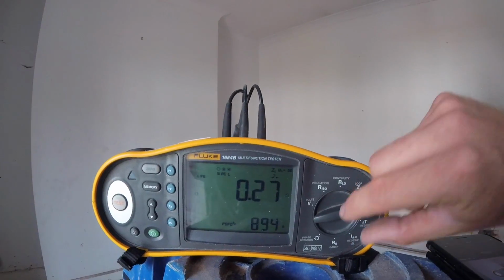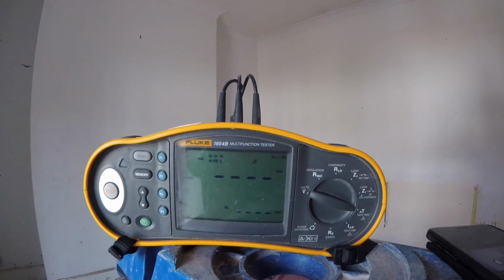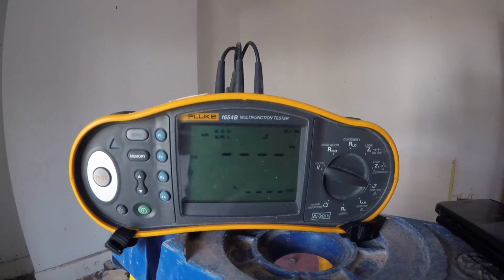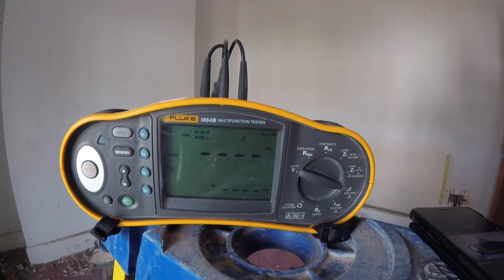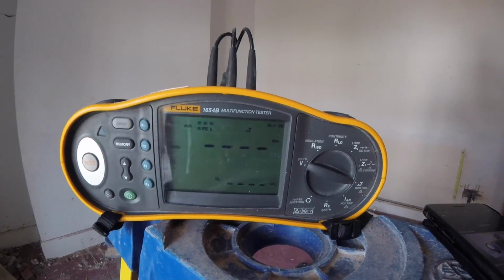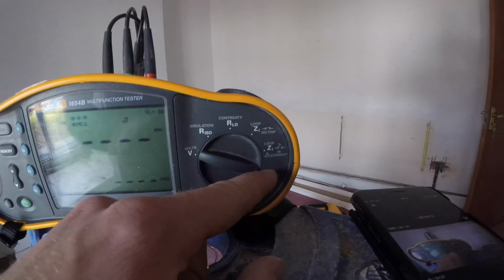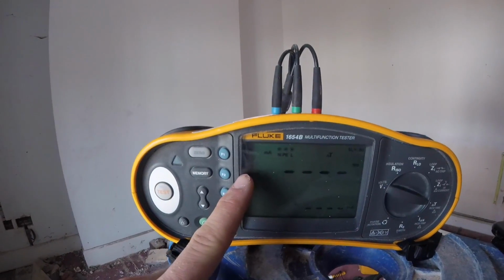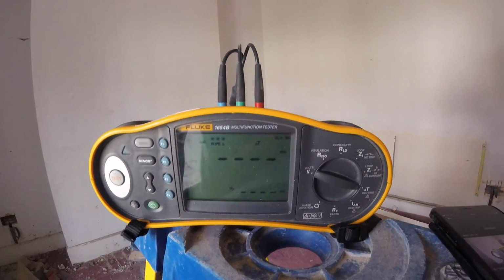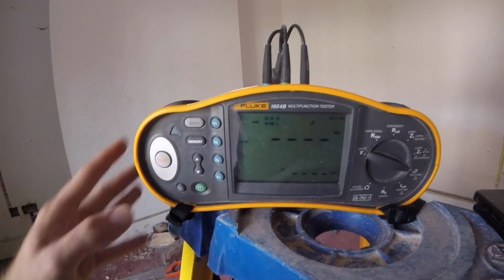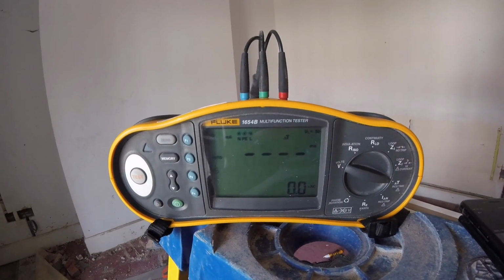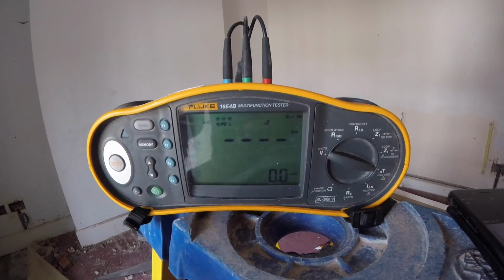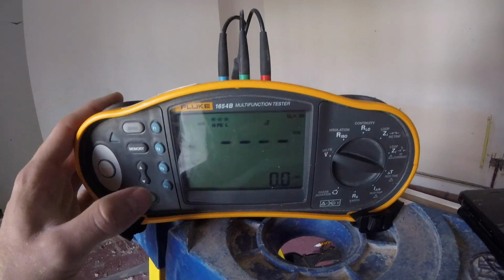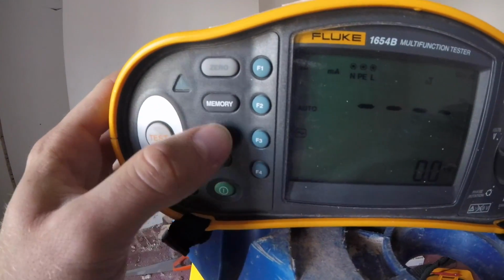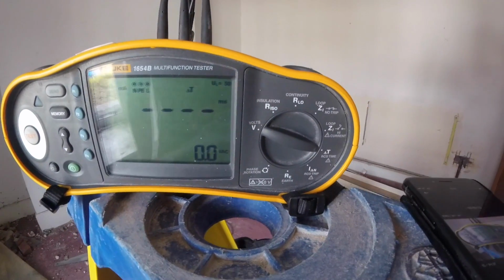So the next function of this meter is the RCD trip times. So when you're doing your tests on your RCDs, just make sure they're tripping within the required times. You literally just set it on your trip, and it's got an auto function on here, so you can see there it says auto, and all you do is plug that into a socket, for example, press test, and that will run through all the tests, half times, 1 times, 5 times on each side of the wave, and then display a figure on there which you can just run through by pressing up and down here. So yeah, that's quite handy.